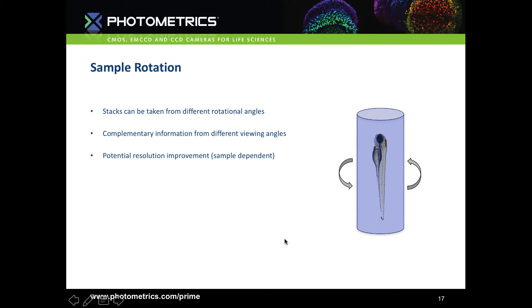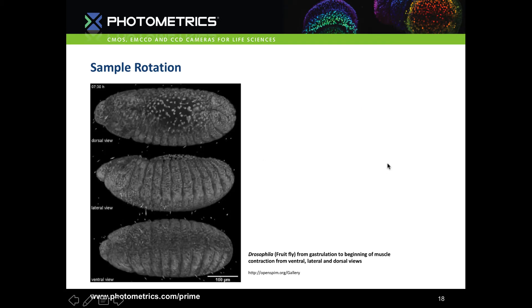Rotation adds an extra advantage: we can take image stacks from different angles on the same sample — at 0, 90, 180 degrees and so on — providing complementary information that increases resolution. It's also possible to register and fuse Z-stacks from different rotational angles to give much higher resolution images than the originals. For example, rotational views allow imaging of the dorsal, lateral and ventral views of a fruit fly undergoing gastrulation, telling us more about dynamic live processes than imaging from one side alone.